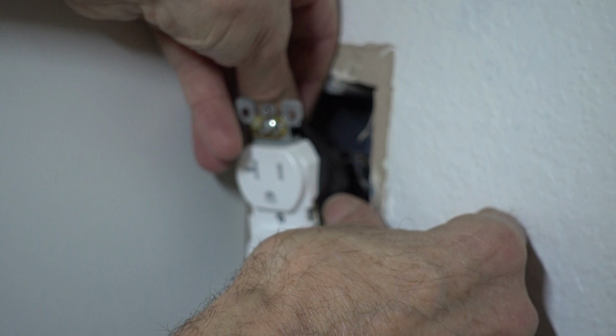I tracked down the wires to the circuit breaker at the main panel, and there were some loose wires connecting the circuit breakers and the panel. Once those were tightened up, we were getting full voltage at the outlet. We put the old outlet back in, and I'm going to return the new outlet to the store. So that was a stupid thing on my part, and maybe you'll learn something from my mistake.